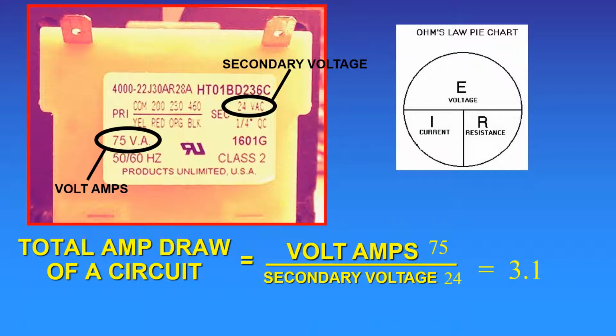By using Ohm's law, we can determine the total amp draw a transformer can handle. In this example, our transformer has a rating of 75 VA. When we divide 75 by the applied voltage of 24 volts, we find this transformer will be able to handle a 3.1 amp load.